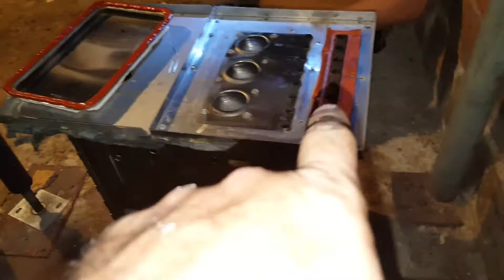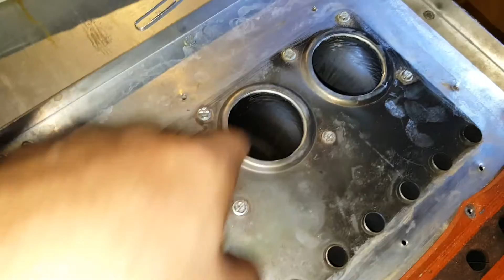Okay, so we've married the primary to the secondary, and that's our seal over the collector box, because this is where the primary heat exchanger dumps into the secondary. These are the inlet of the secondary, and this will be the outlet. The collector box is going to go over this. This unit has its own collector that goes from primary to secondary, and that's what that cap is. We're going to seal him up next.